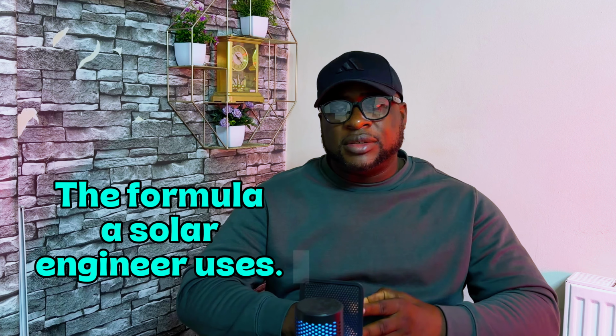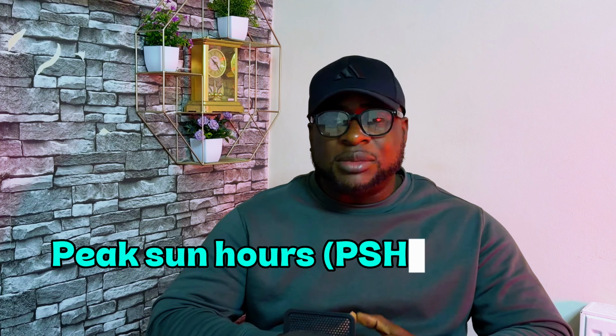Now let's talk about the formula a solar engineer uses, considering the three main inputs. One, solar array size. We are going to be using 5 kilowatt peak for this example. Two, the peak sun hours, PSH, for Lagos. This is not the same as daylight hours. It is the equivalent number of hours at maximum solar intensity.